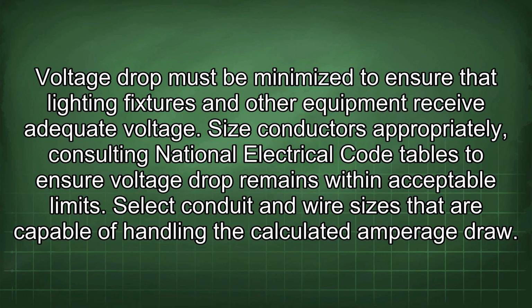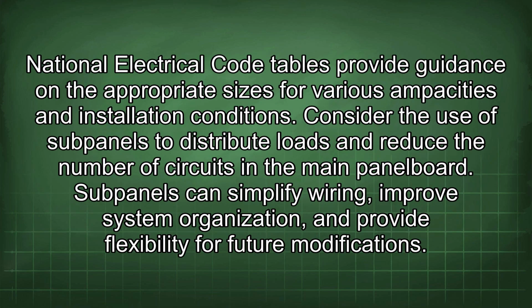Size conductors appropriately, consulting National Electrical Code tables to ensure voltage drop remains within acceptable limits. Select conduit and wire sizes that are capable of handling the calculated amperage draw. National Electrical Code tables provide guidance on the appropriate sizes for various ampacities and installation conditions. Consider the use of subpanels to distribute loads and reduce the number of circuits in the main panel board.